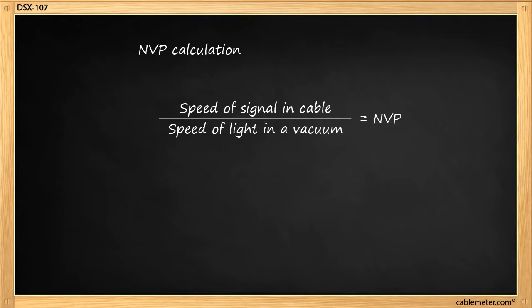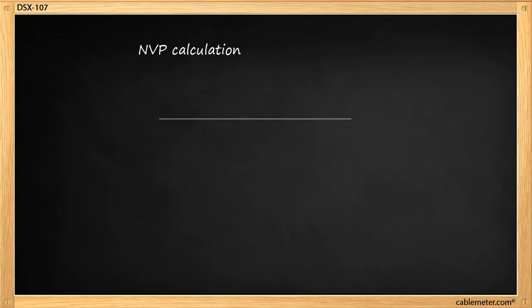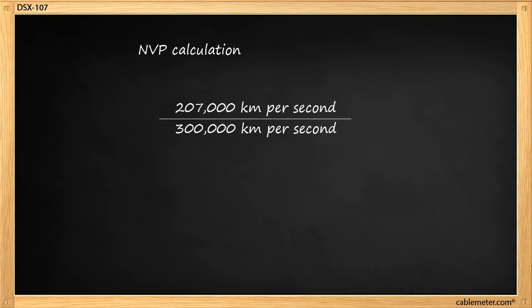NVP is calculated by taking the speed of the signal in your cable and dividing it by the speed of light in a vacuum. A typical value for a signal in a cable may be 207,000 kilometers per second. The speed of light in a vacuum is 300,000 kilometers per second. That gives us an NVP of 0.69 or 69% in this example.